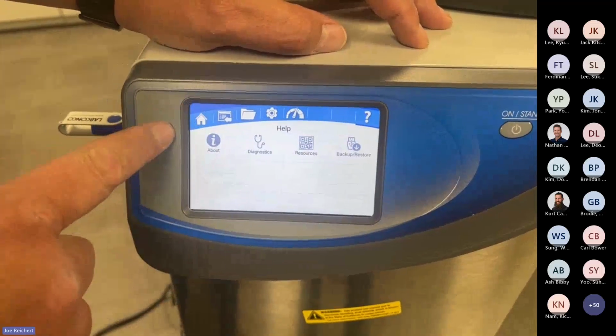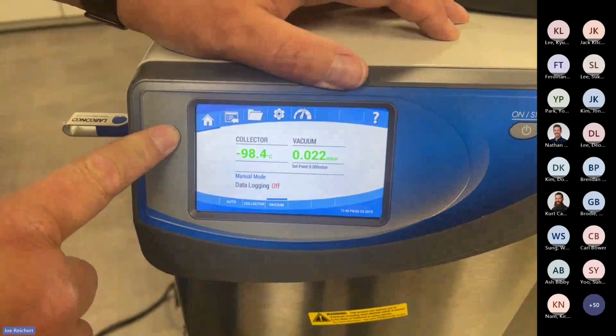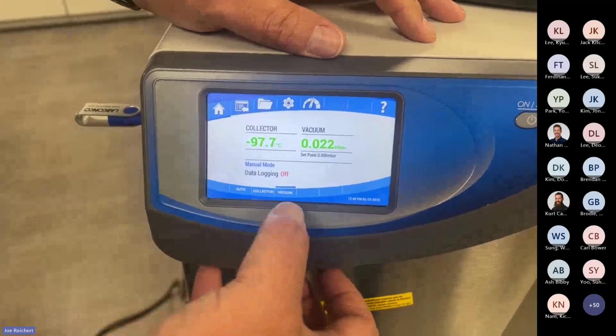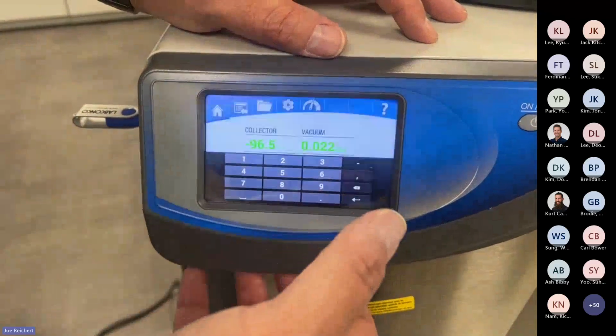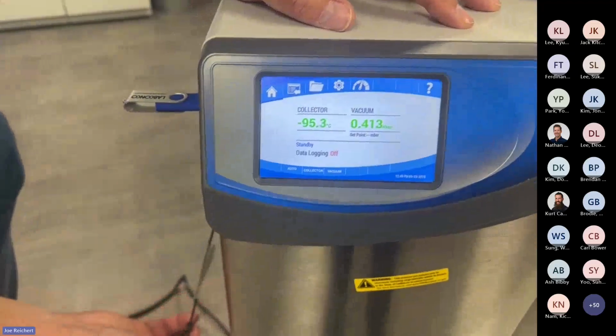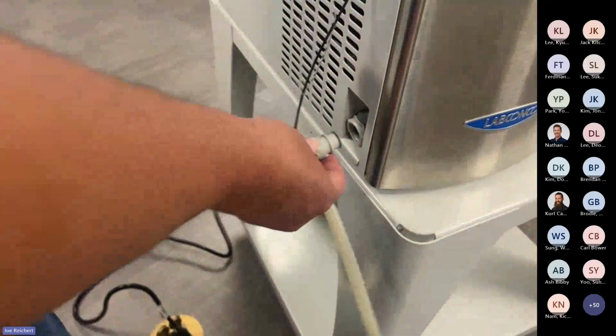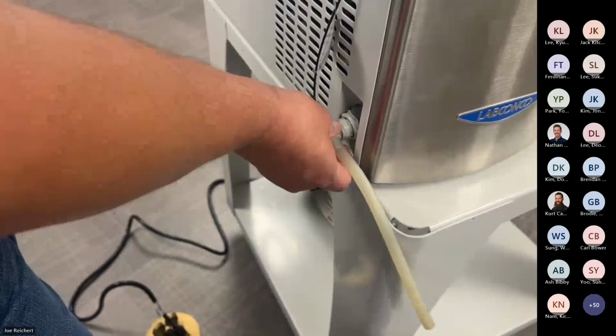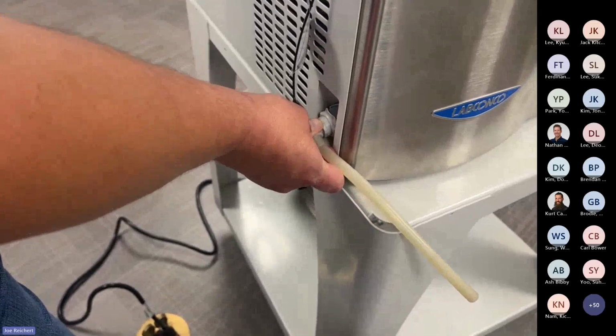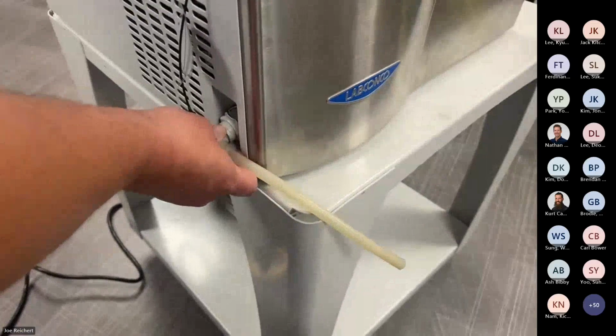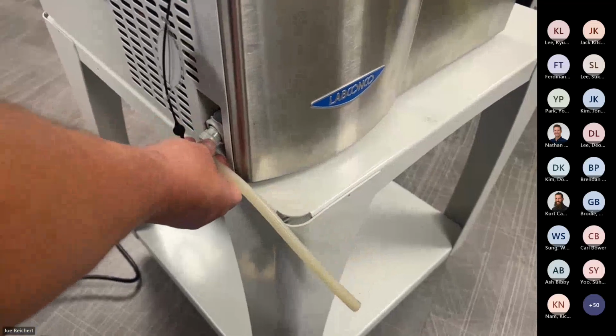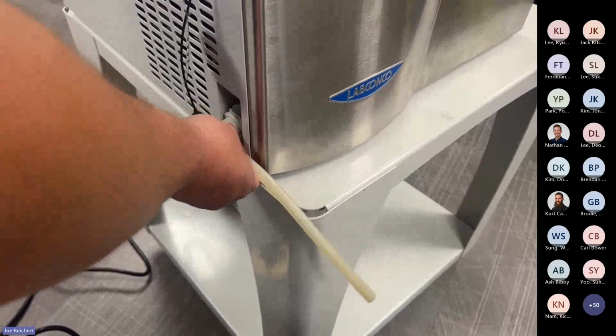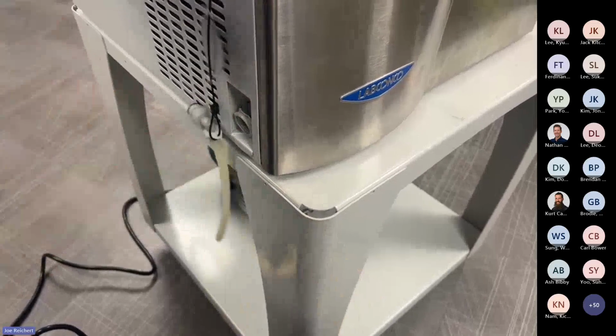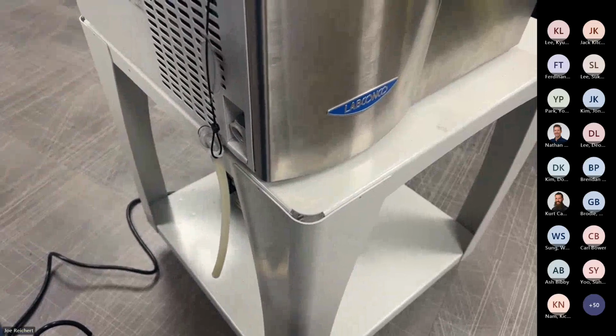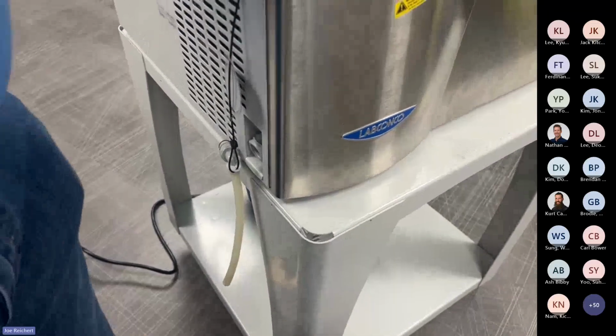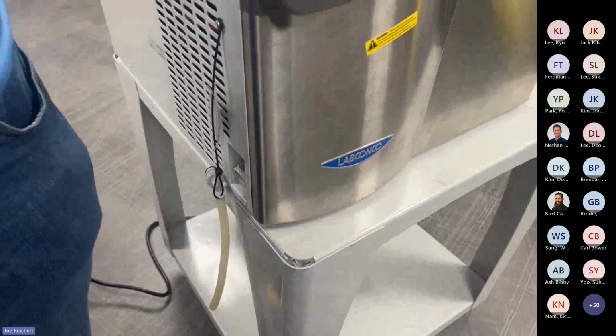But to try to do troubleshooting on these units, I'm going to stop the vacuum pump for a moment here. And then I'm going to bleed the pressure out from the side. Since I have no chamber on top, I'm just going to use the drain port. Okay, so now I can remove everything off the top. And we can always install the 12-port chamber.